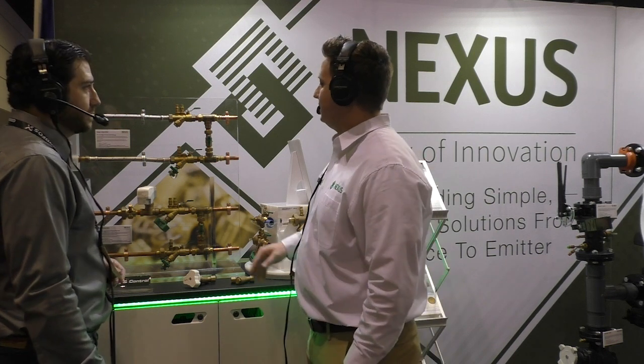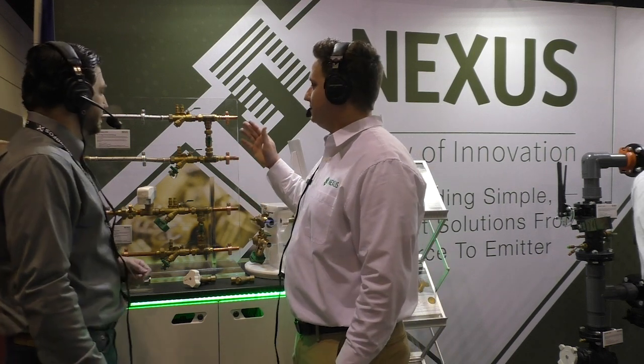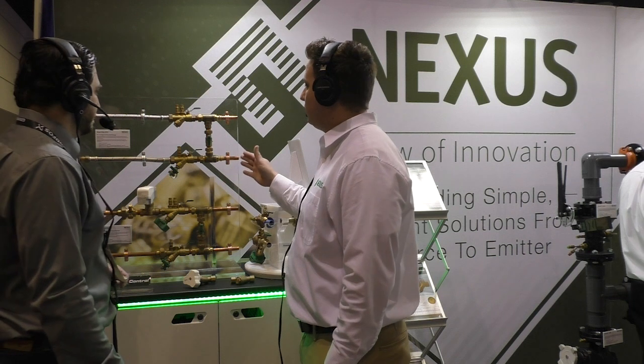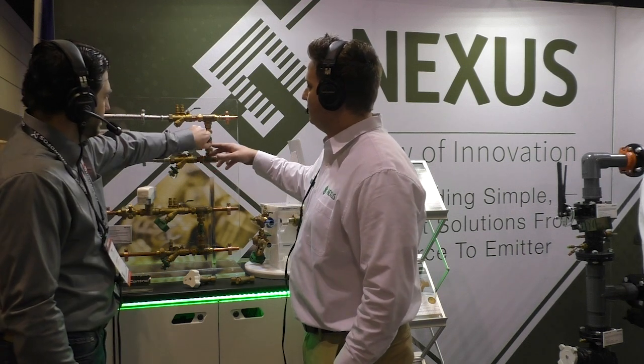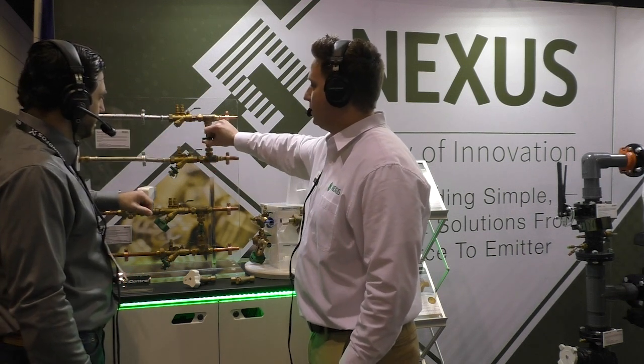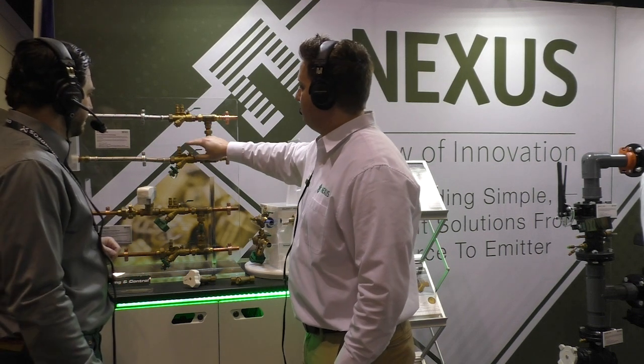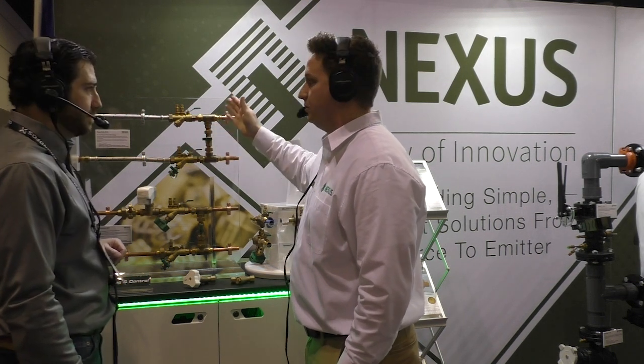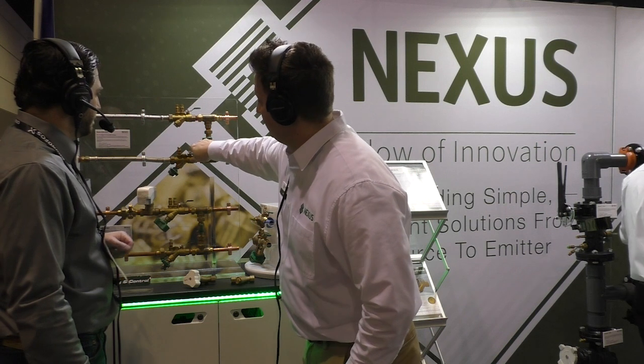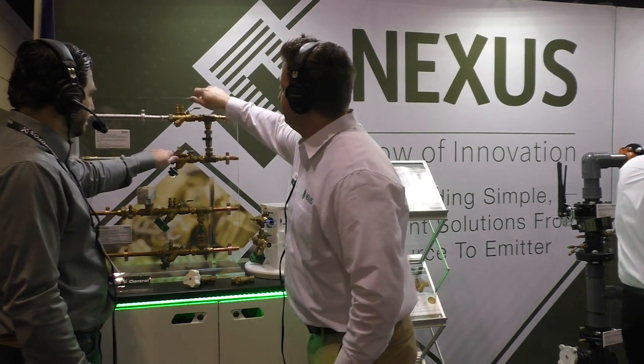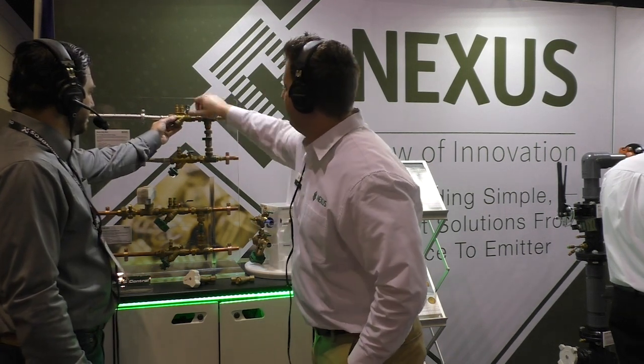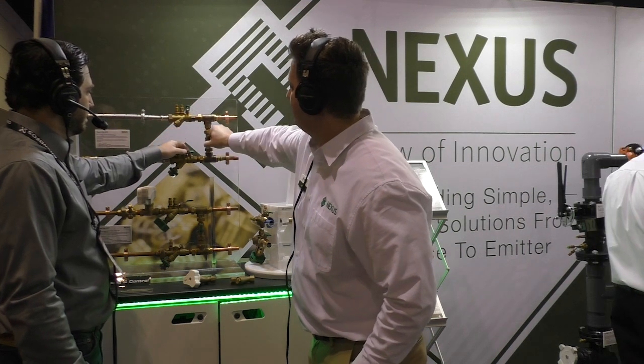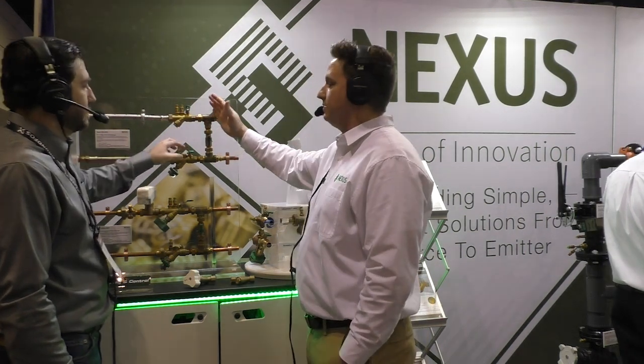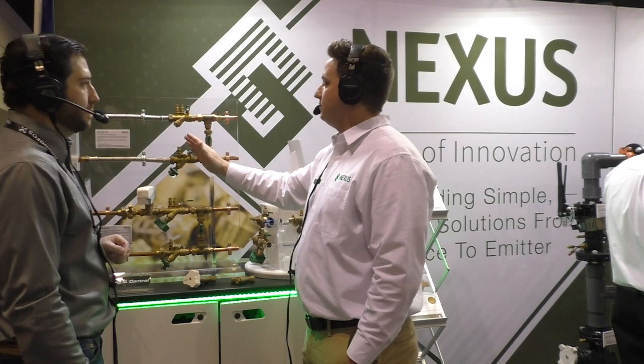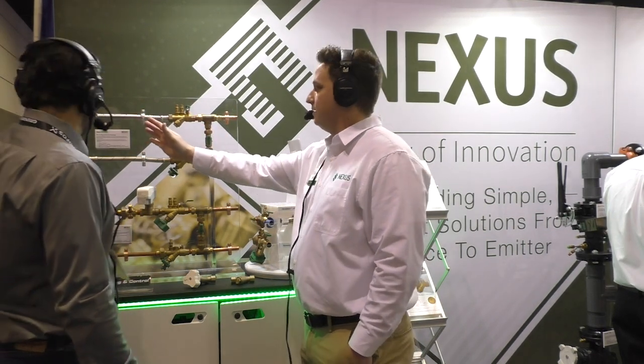The bypass kit is primarily used as a flushing kit. You want a way to isolate, so typically this will be closed in operation. As soon as you want to bypass or flush the system, you would turn this one here, turn this one up here, open this guy up, and now you have complete isolation from any of the equipment.